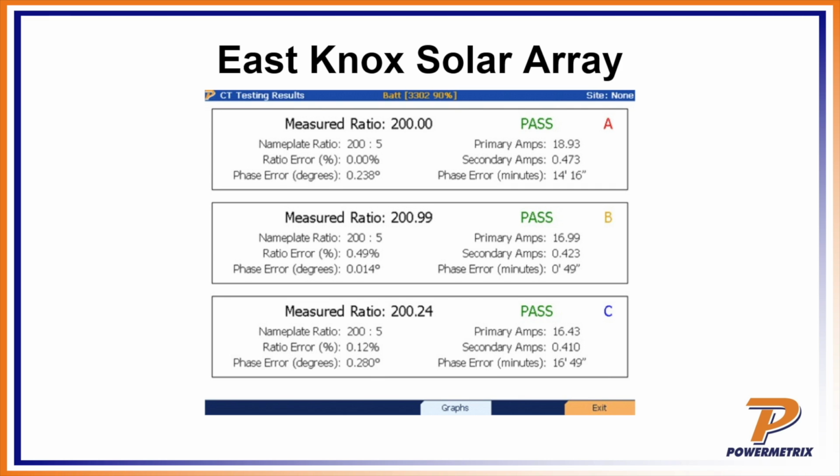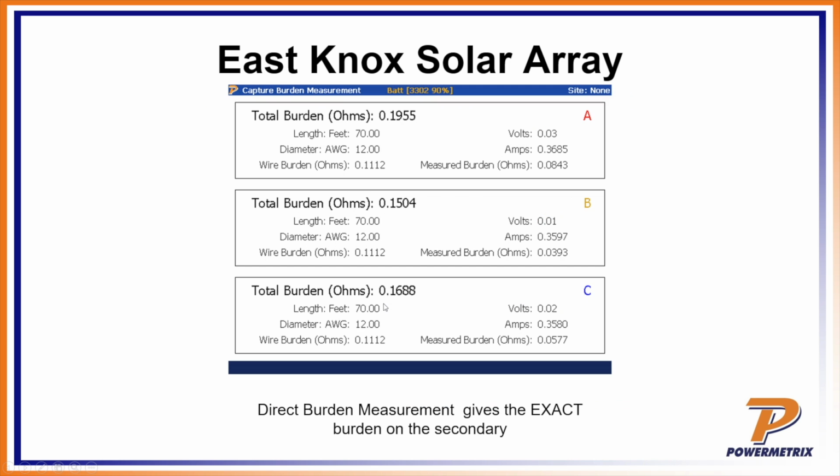And so here's a picture of the results. Once again, excellent results. Those were 200:5 CTs, and so we have very low ratio errors. The phases are actually also quite good. So this site was remarkably good when we ran through that.